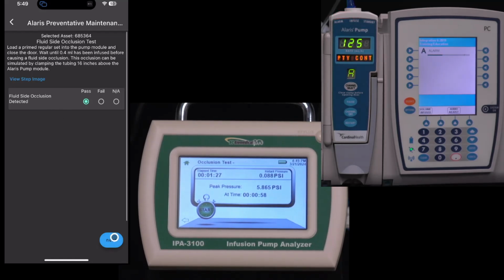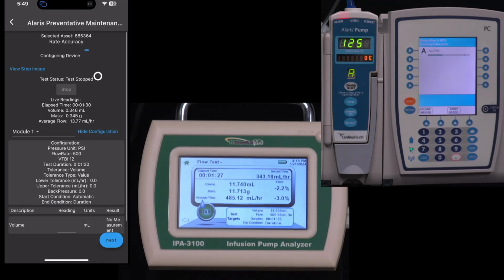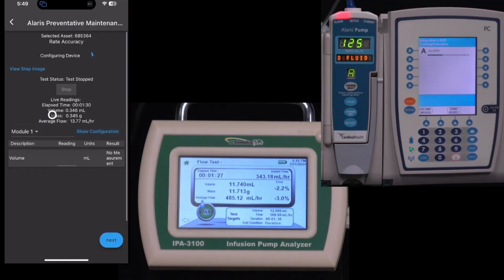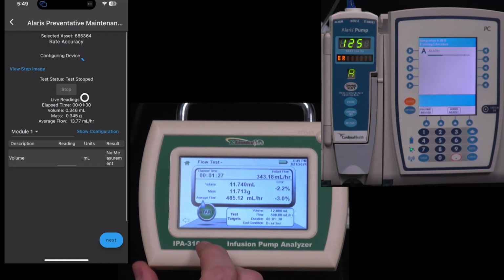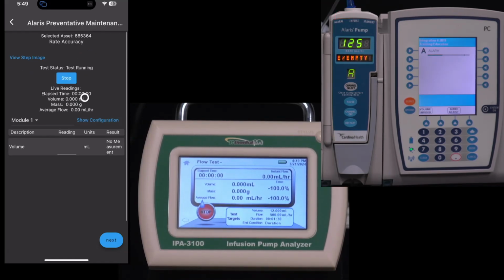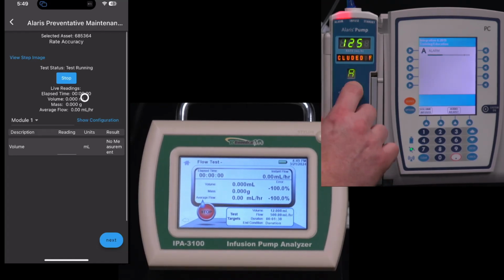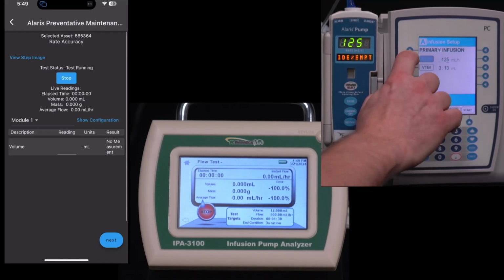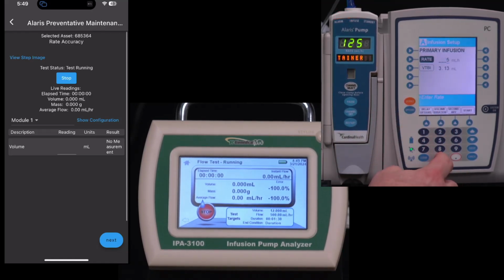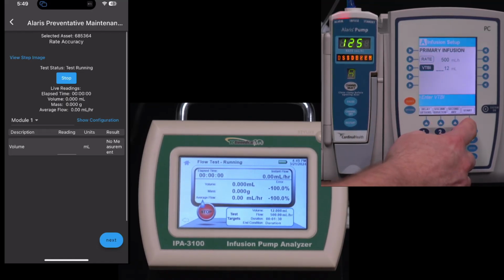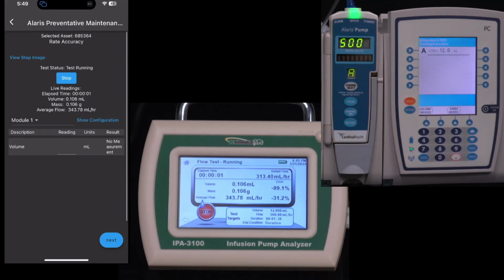Okay, so we passed that step. And next we're going to do a flow test. So we've got our readings again here on the screen. So I'm going to go ahead and start it. It sent all the settings to the IPA and it started the test. So all I have to do is configure the pump and select the channel. Now these flow tests are done at 500 milliliters per hour, just like we did before, and 12 milliliters. And we'll go ahead and start that test.